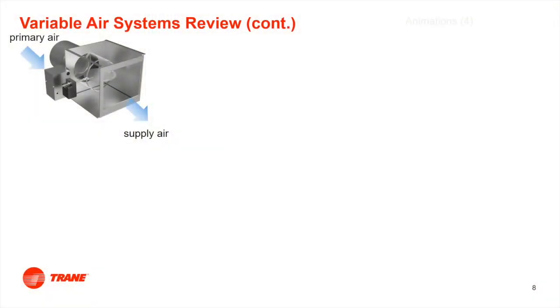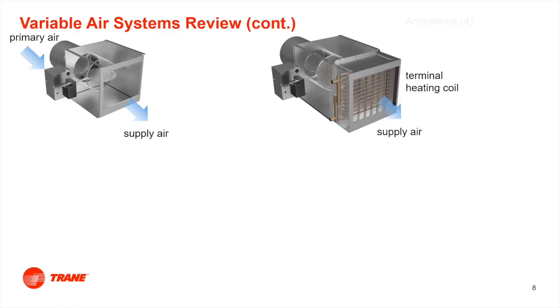But what if we want to reheat that air? What if we want to heat that room up? What if it needs heat and the room next to it doesn't? We can simply take that cooling VAV and add a coil to it. That coil can be hot water, that coil can be electric, and that way we are no longer dependent on the rooftop to provide heat. We know it's doing 55 and 1 inch, now we can provide heat to that specific space.